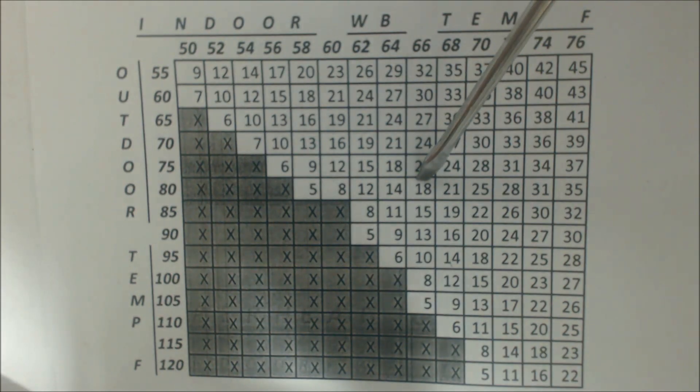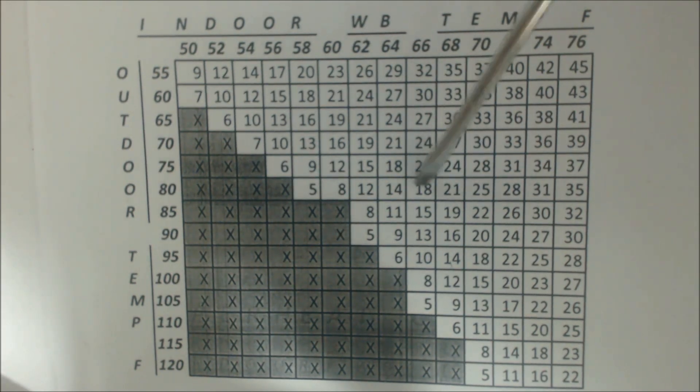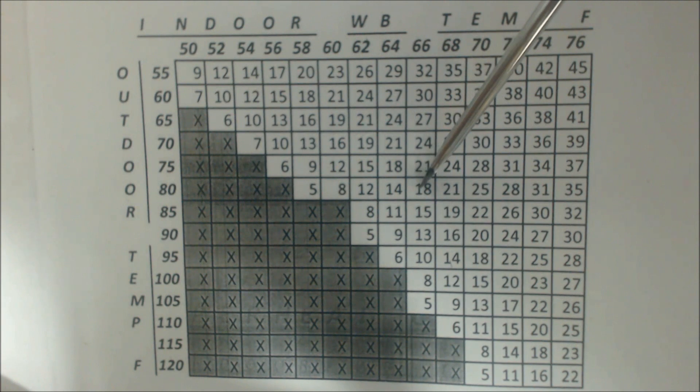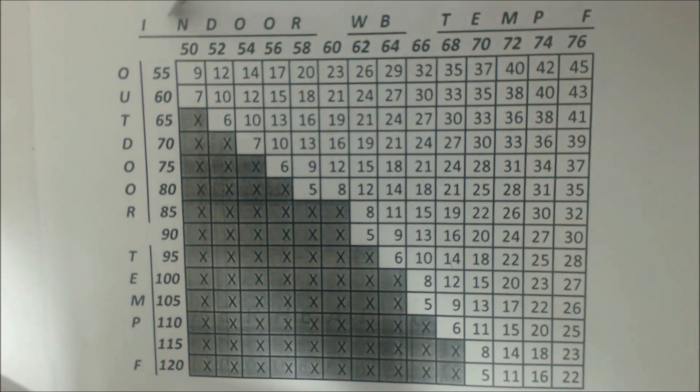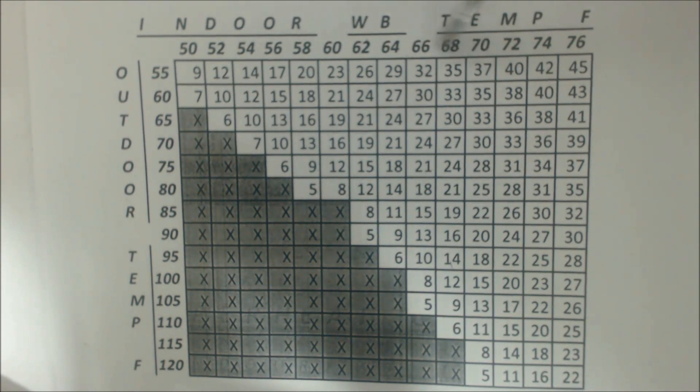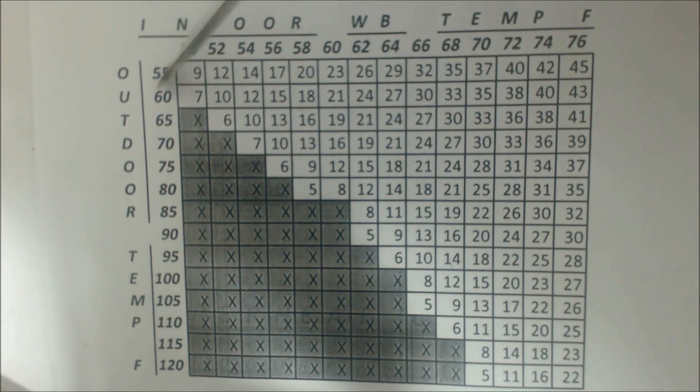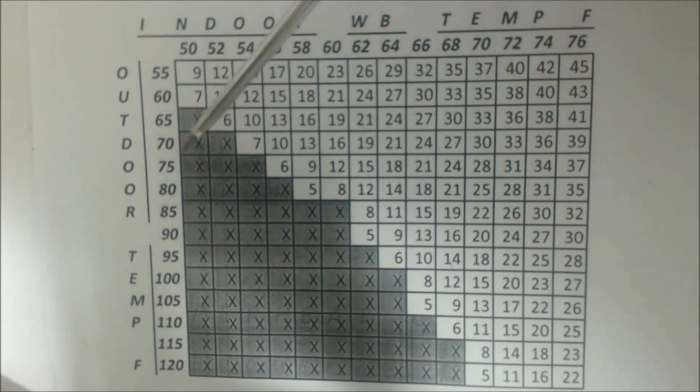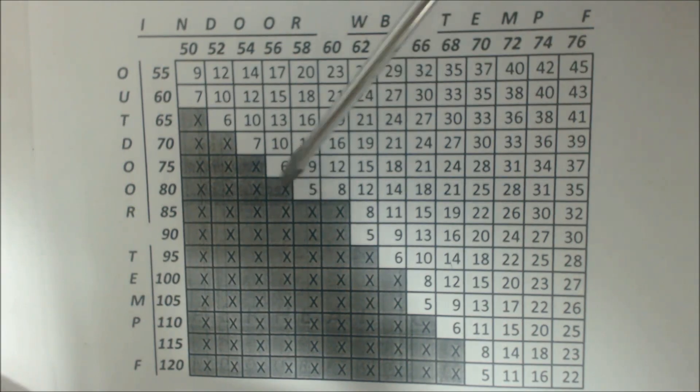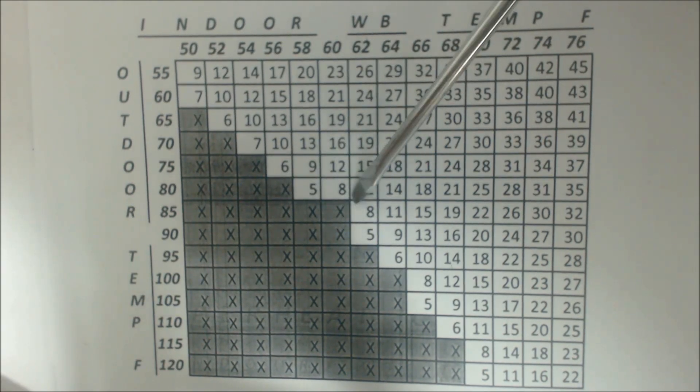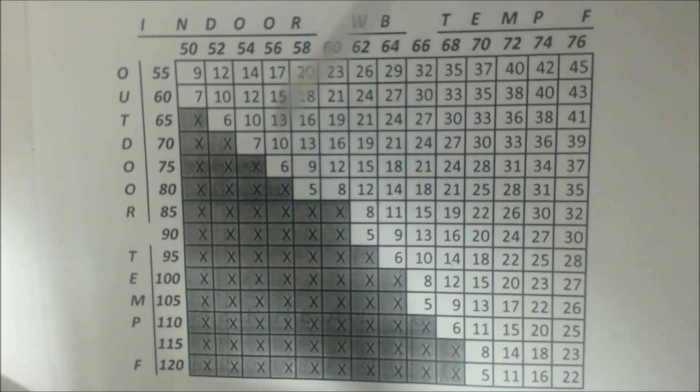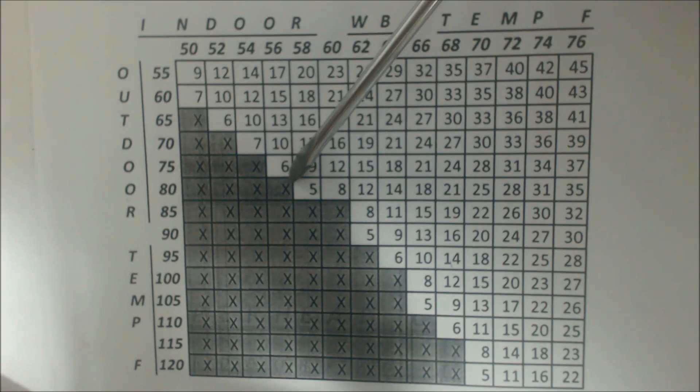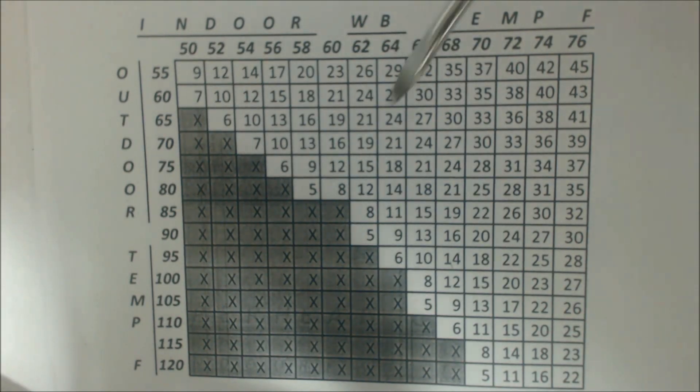You want to get the piston or orifice charge in superheat very close to the target superheat. Because depending on whatever the wet bulb temp is in the house, as the wet bulb temp gets lower and say you fall into this particular outdoor temperature, your superheat could be down real low like eight degrees of superheat or six degrees, and you want to make sure that you have enough superheat to where you don't have liquid getting back to the compressor.